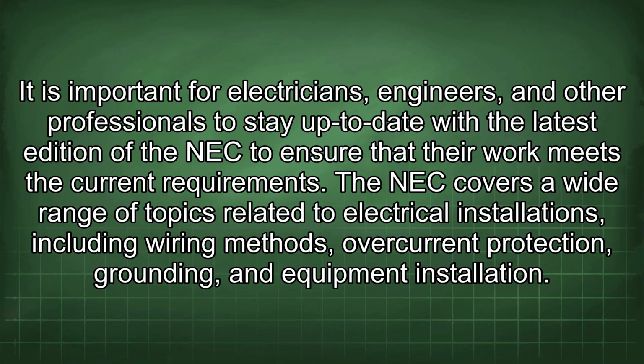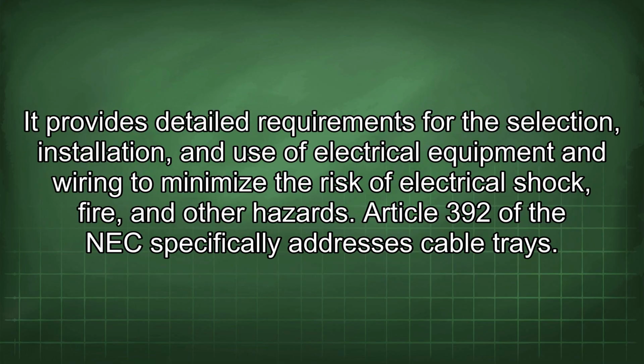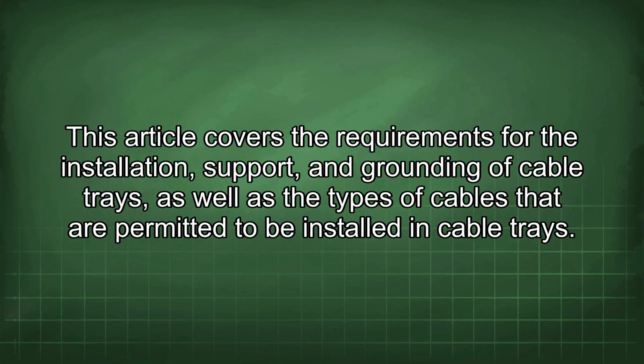The NEC covers a wide range of topics related to electrical installations, including wiring methods, overcurrent protection, grounding, and equipment installation. It provides detailed requirements for the selection, installation, and use of electrical equipment and wiring to minimize the risk of electrical shock, fire, and other hazards. Article 392 of the NEC specifically addresses cable trays. This article covers the requirements for the installation, support, and grounding of cable trays, as well as the types of cables that are permitted to be installed in cable trays.